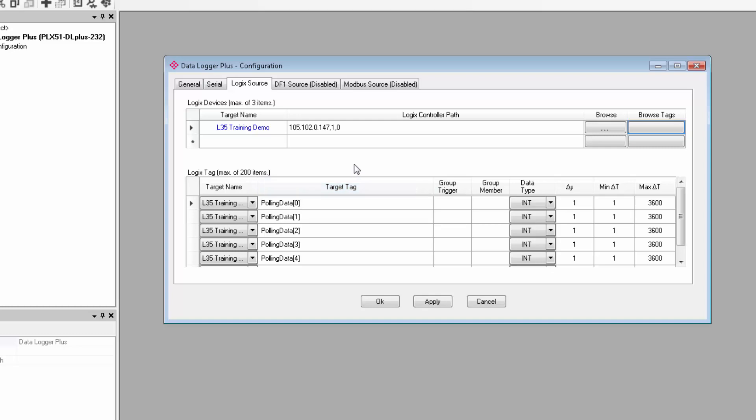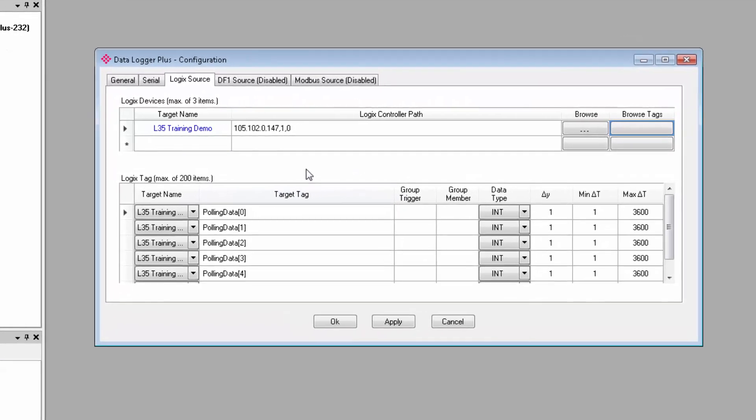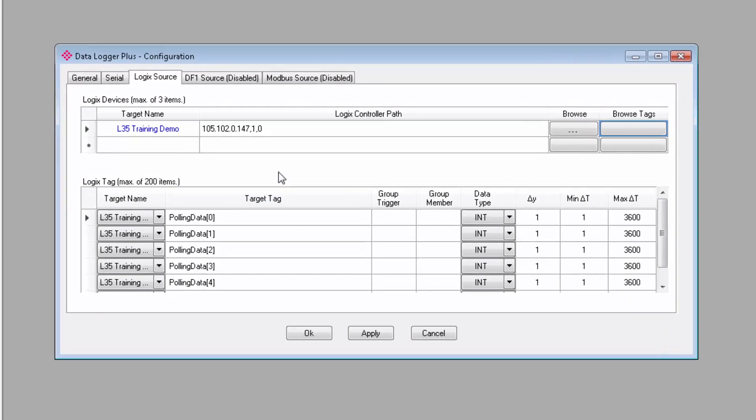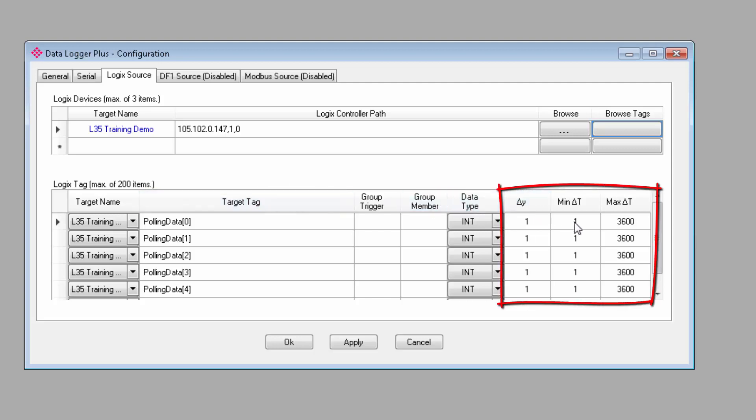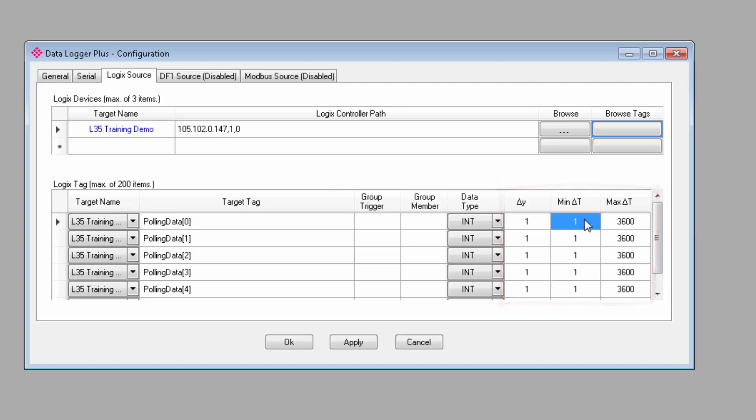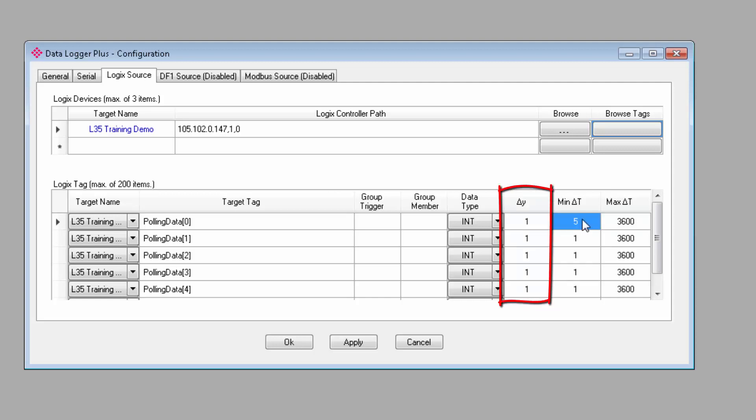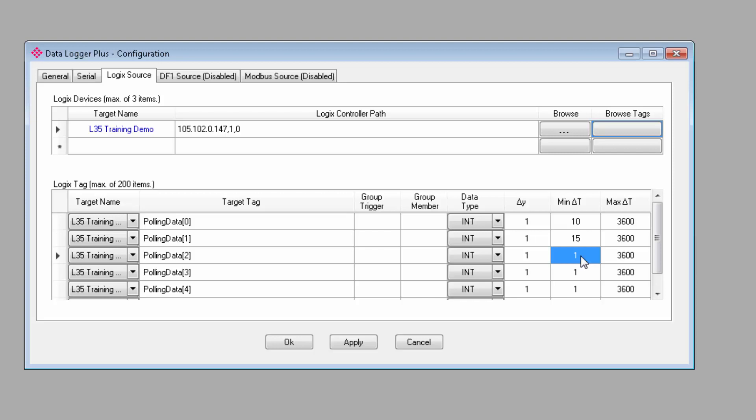Now from here, we have some options to define how often and under what conditions we want to log values from each of the tags. On the right, we have the three parameters to configure when data should be logged. The first two, the delta y and minimum time, work in conjunction with each other to ensure tags are not logged too frequently. The last one is the maximum time between logs. Delta y is a simple value change. So if we leave it at 1, any time the value for the tag changes by 1, up or down, it will be ready to log the tag. And it would then wait for the minimum time interval between logs to elapse before logging the tag.